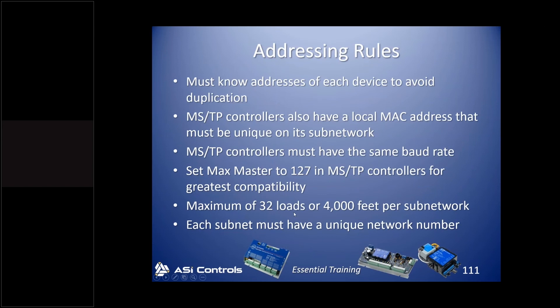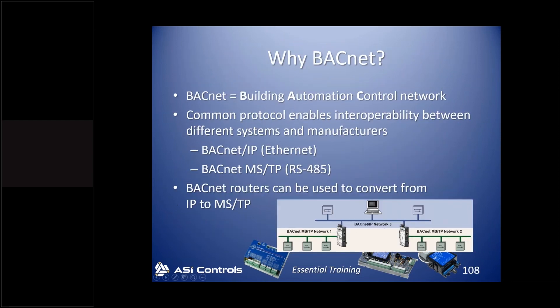Recapping from Tech Note 23: the maximum is 32 loads or 4,000 feet per sub-network. Every ASI controller is a full load controller. If integrating with other BACnet MSTP controllers, you might see half-load or quarter-load devices, so do the math accordingly. Each sub-network needs a unique network number — whether it's an IP network or an MSTP network. So in a setup with one Ethernet network numbered 3 and two MSTP networks numbered 1 and 2, those are three distinct networks.